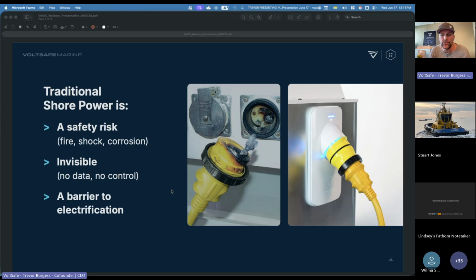And the salt water does the rest and turns a shore power plug into the equivalent of a toaster. This is where you see meltdowns, fire risk. Then we have other issues, a very systemic issue that needs to be corrected and is in the process of being corrected: current leakage that happens from vessels into the water. It's systemic because governing bodies until recently never required ground fault protection for anything above 20 amps, which is your standard home receptacle, GFCI. A GFPE is the same thing as a GFCI, except it has a trip sensitivity that is less sensitive than a home version, and it's becoming a requirement at every slip.